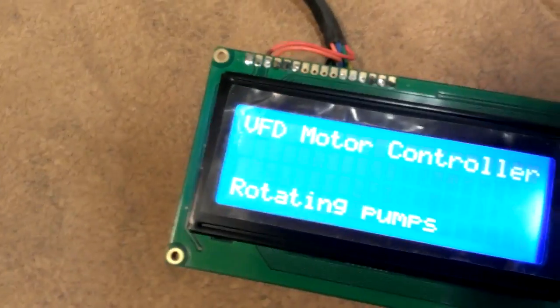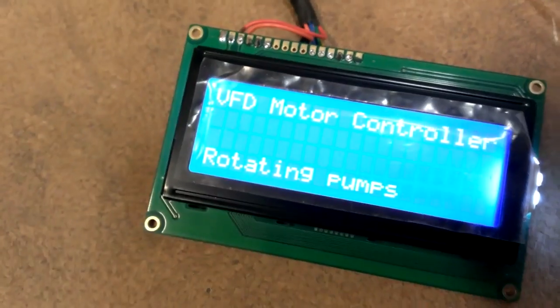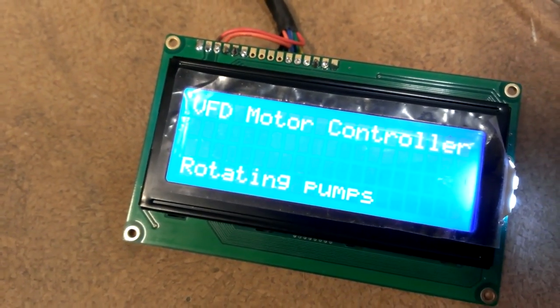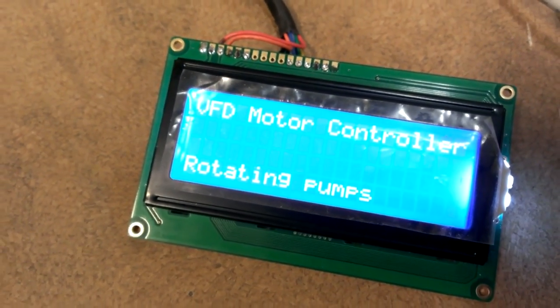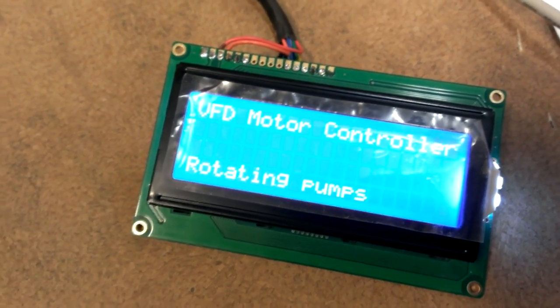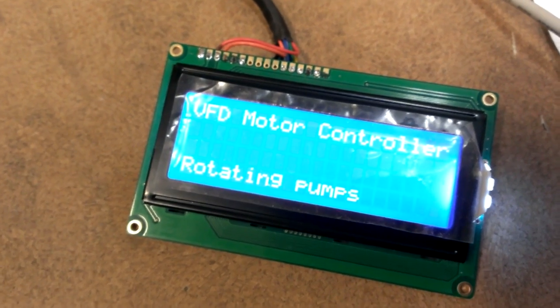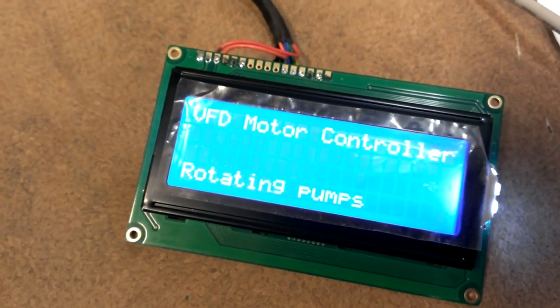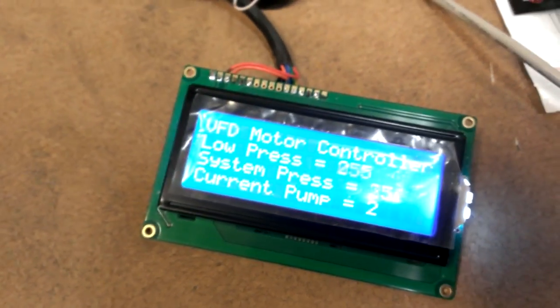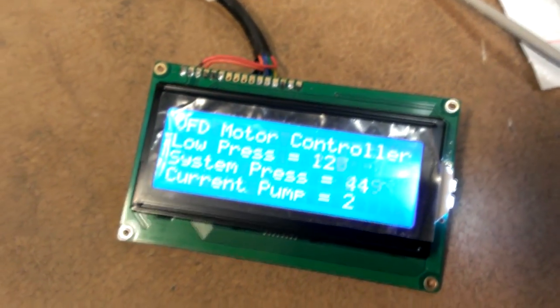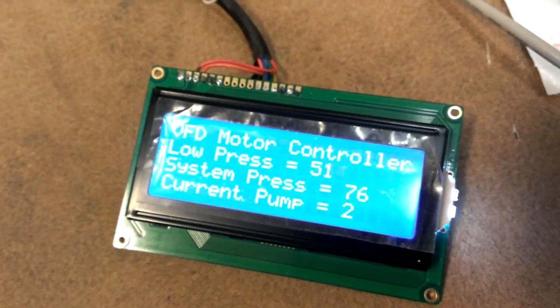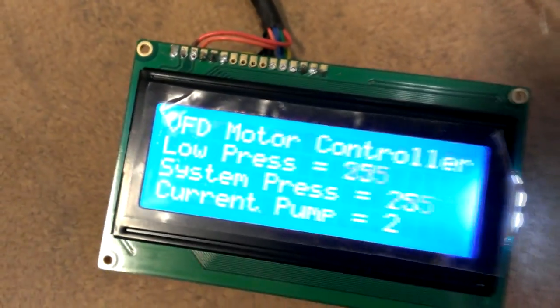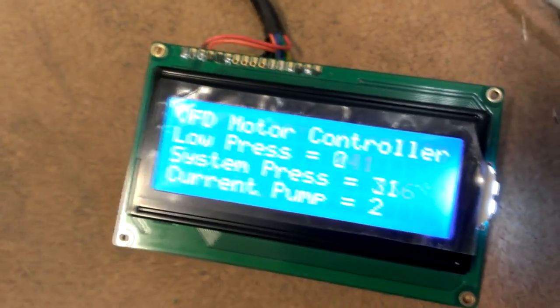I want to rotate them. Put the switch. It's going to go through a rotate pump sequence, which stopped the VFD for five seconds. Then it switches the pump contactor. And then five seconds later, the VFD starts back up. And then we're back in regular monitor mode.